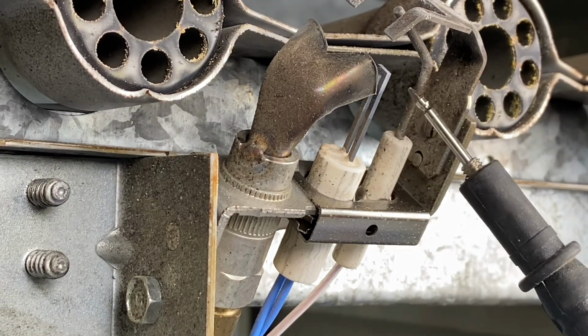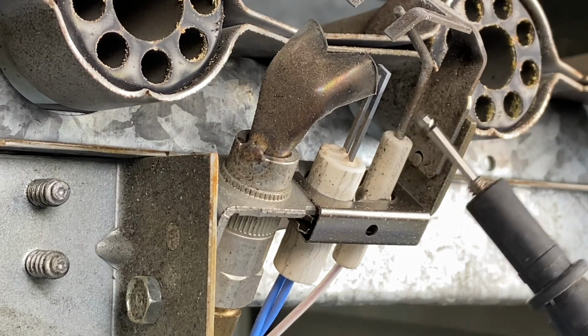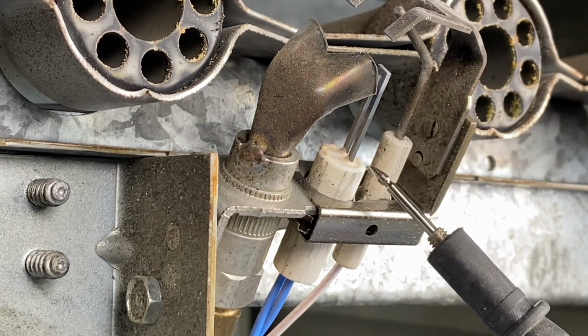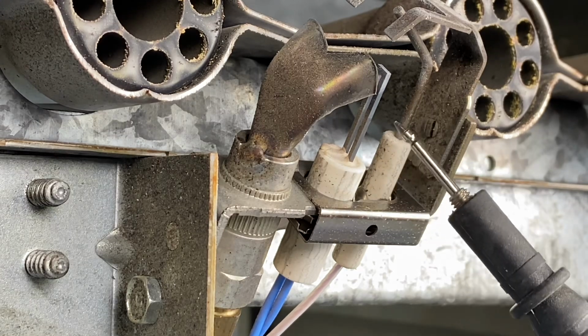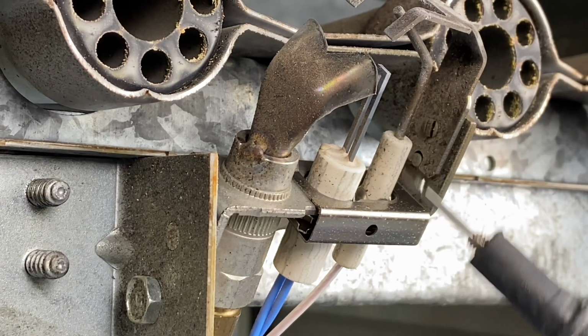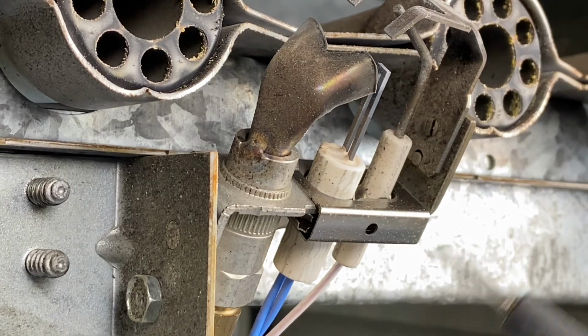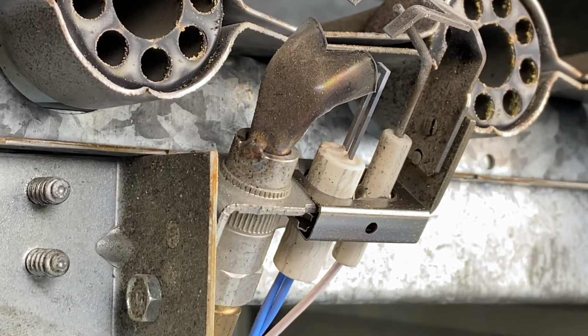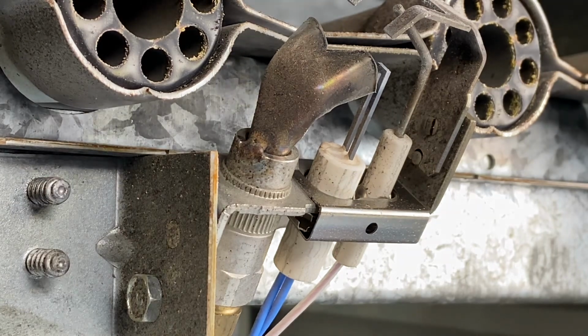If you were to touch this with your fingers, sometimes it would leave an oil stain on there, which would cause them to break out even faster. Also, dirt in the system would cause these to fail. So this is our intermittent pilot system. For what it's worth, hopefully you're not going to run into these much in the field anymore, but there's still a ton of these out there.